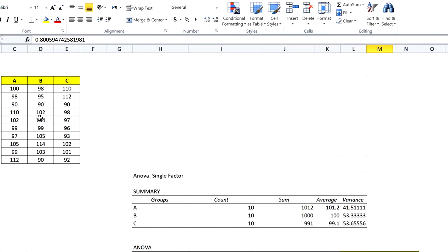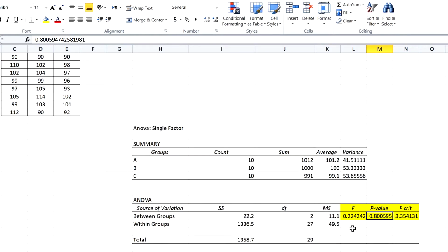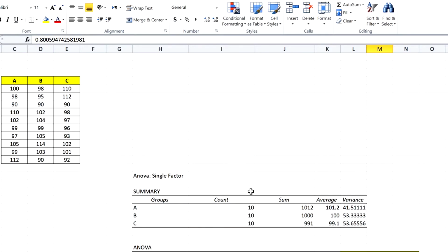And that means if you have two instruments in your lab and you bought another instrument and you want to check its performance, you will analyze, as we did, replicates of samples spiked with a known concentration. Then if you find that there is no significant difference, all of these instruments can be used to analyze these target analytes and get accurate and reliable results. So the performance of these instruments is equal.